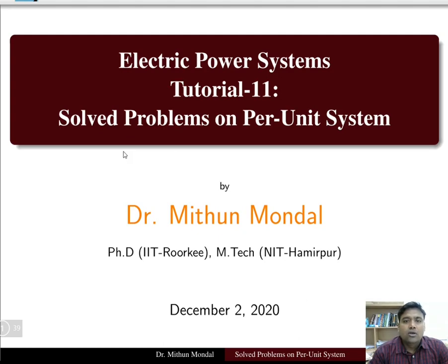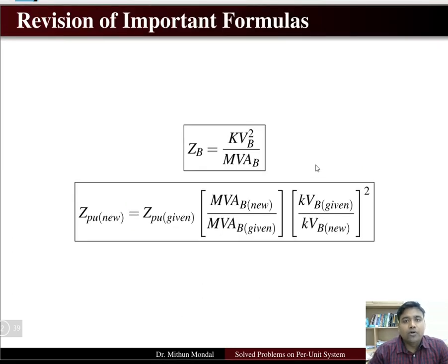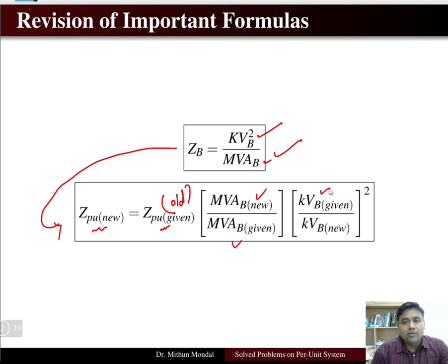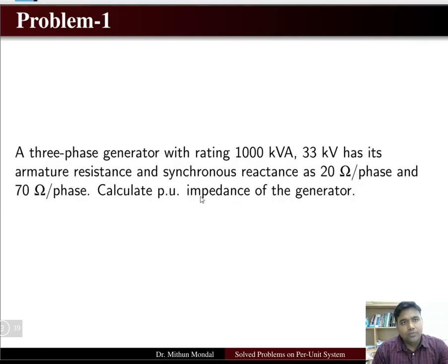Welcome to the next tutorial on electric power systems. We are going to discuss the per unit system. Let us revise some important formulas used to solve the problems. The first formula is to determine the base impedance: base impedance equals the square of the kilovolt base divided by MVA base. The second formula is Z per unit new equals Z per unit given times (MVA new / MVA given) times (kV given / kV new) squared. These two formulas are sufficient to solve per unit system problems.